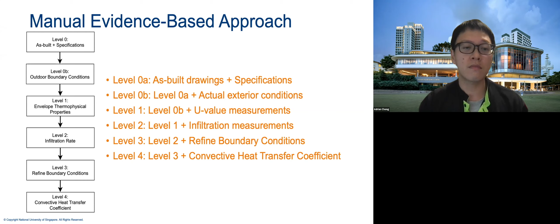This diagram shows how the accuracy of the model evolves. What we can see here is that at level 0, we see some overestimation — it tends to overestimate the indoor temperature during the afternoon. After updating the boundary conditions, interestingly, our root mean square error reduces to about 0.2 degrees Celsius. Typically in most calibration studies, a root mean square error of 0.2 would be considered extremely good enough, and usually that's where the calibration stopped.